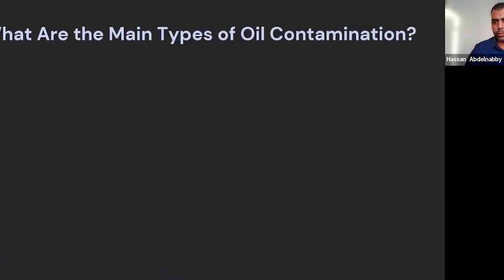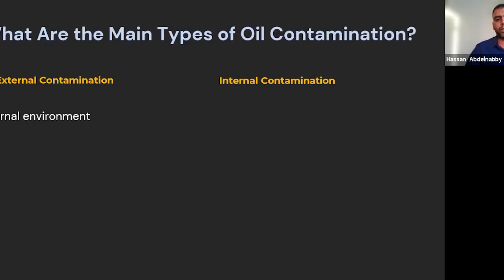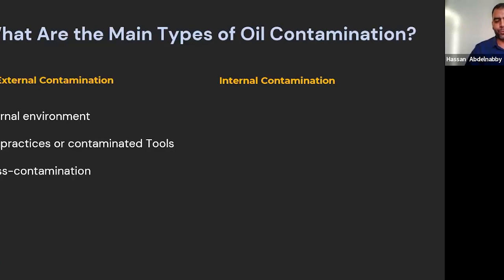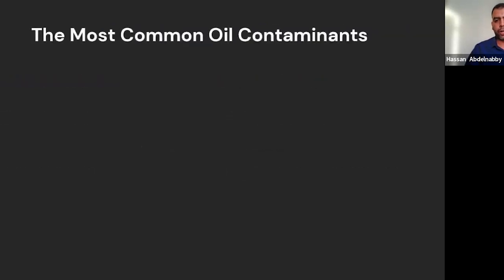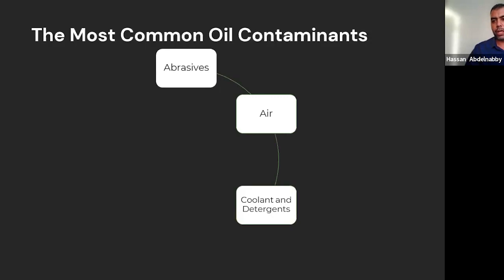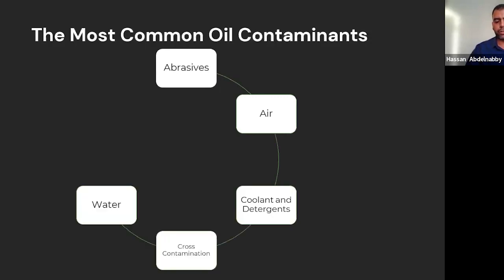What are the main types of oil contamination? We have external contamination and internal contamination. External contamination comes from the environment — dust, dirt, water, humidity, bad practices, contaminated tools, or cross-contamination. Internal contamination can come from surface degradation, oxidation, or at the end of oil life, the depletion of additives. The common contaminants we'll discuss are: abrasives, air, coolant, cross-contamination, water, and fuel.